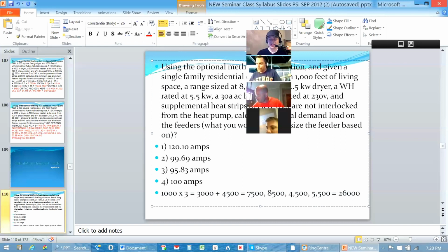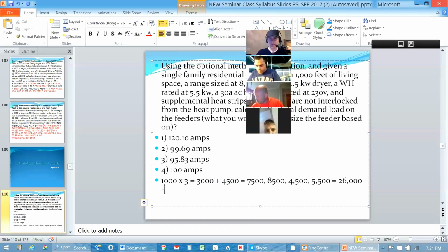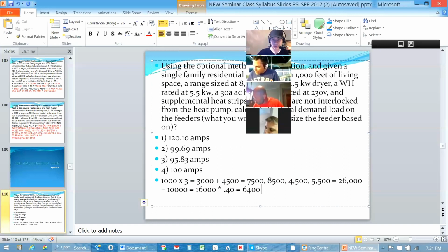And that 26,000, the first where we stop and go up to the top of B, which has our derating steps. I'm going to take the first 10,000 of that at 100%, so minus 10,000 equals 16,000. And at 16,000, I'm taking a derating of 40%, which gives me a number of 6,400. So I got 6,400 with the 40%. I add the 10,000 back to that.